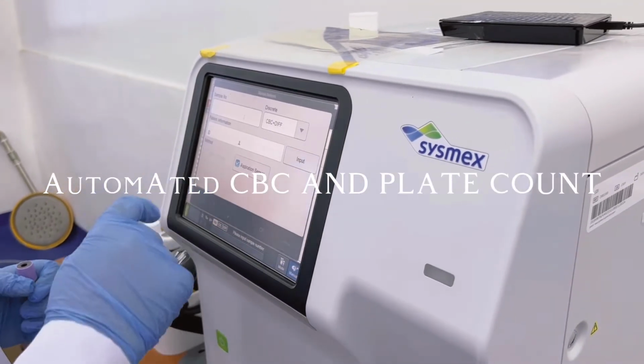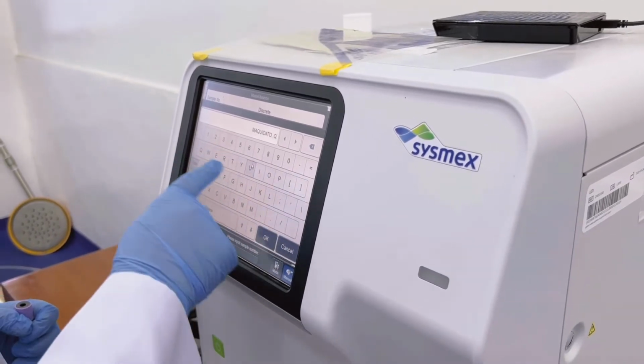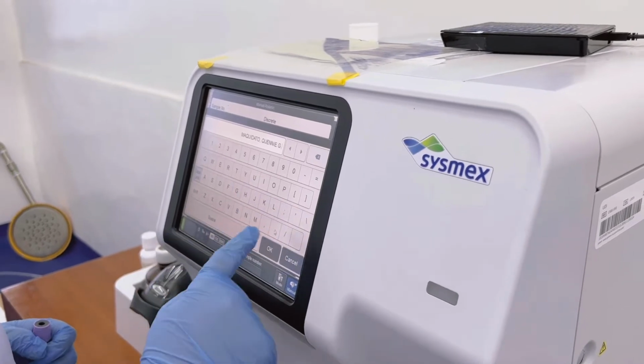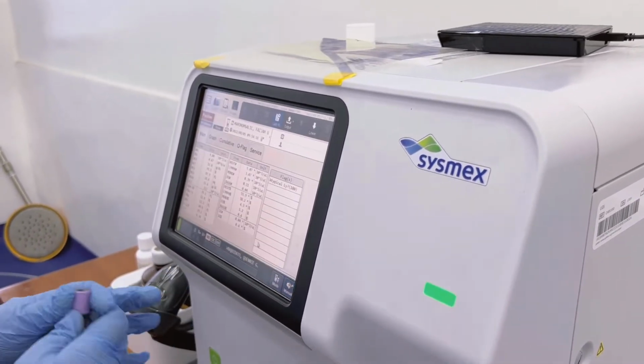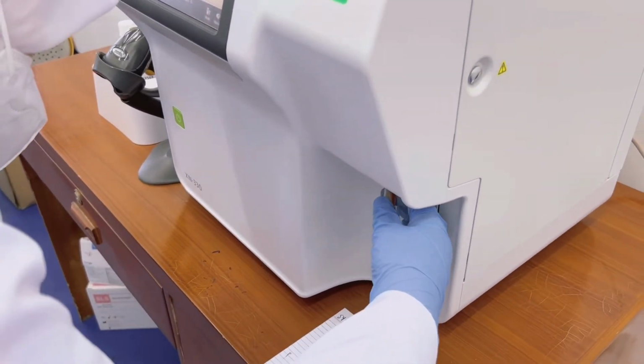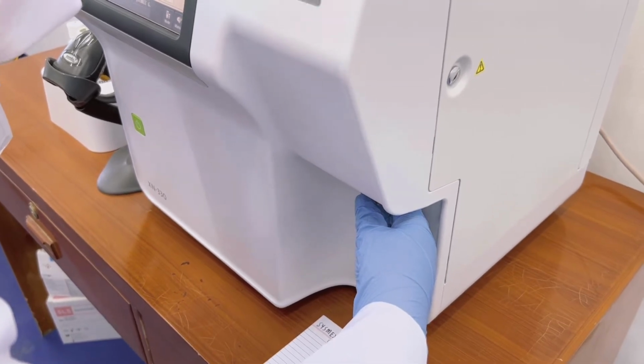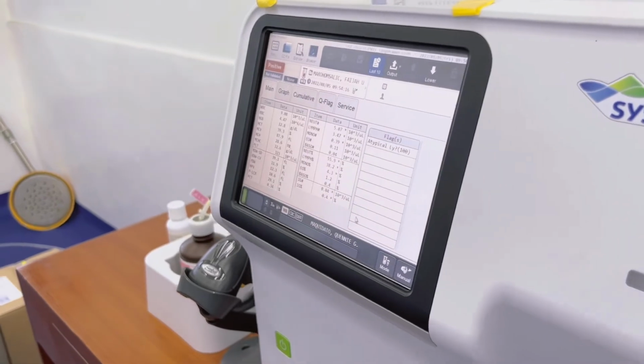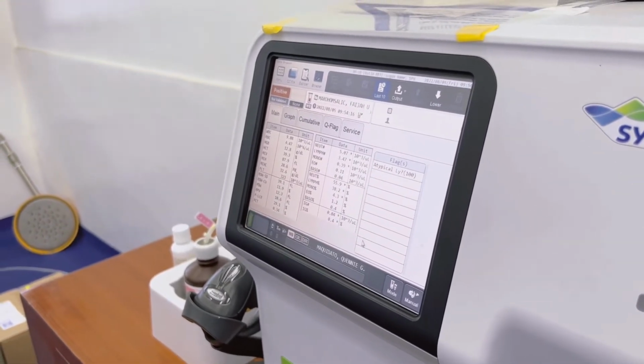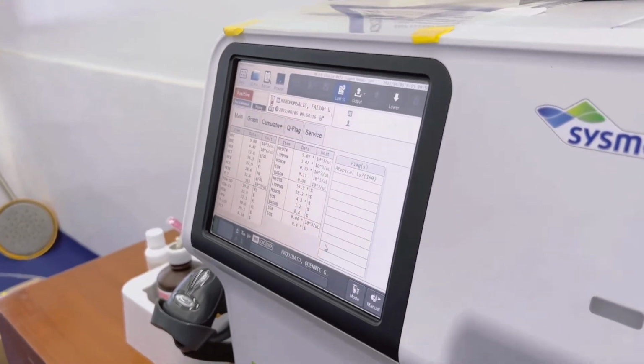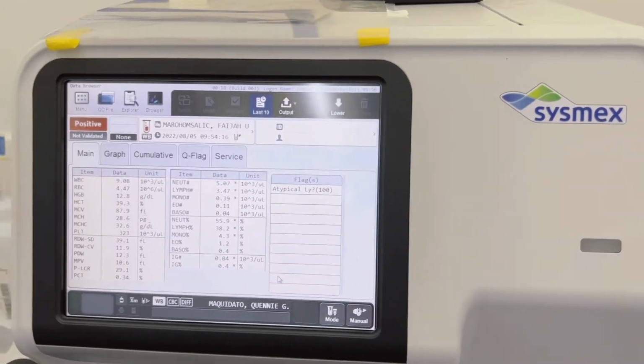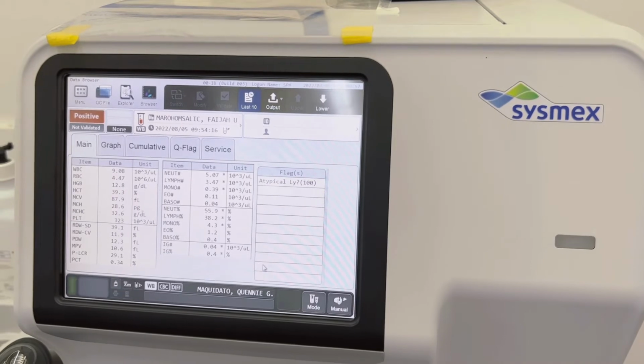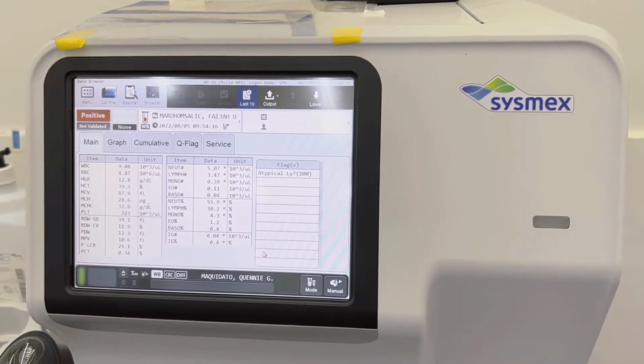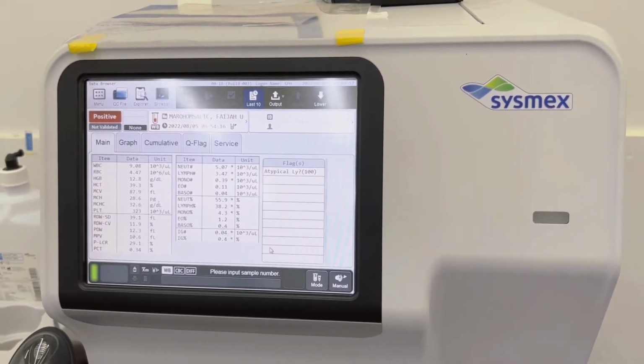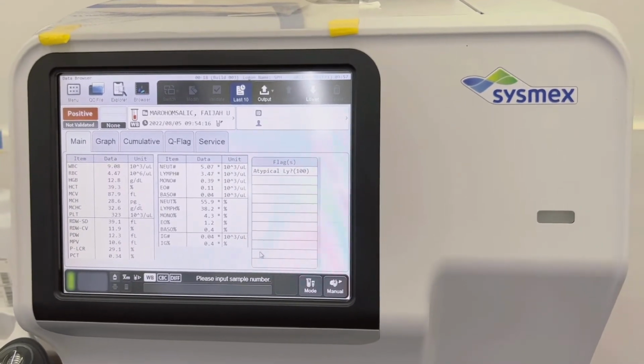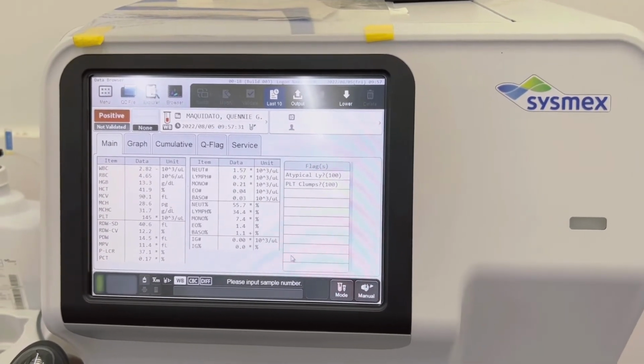Automated CBC and platelet count using Sysmex. First step is to input the patient's information into the machine. Next, you would see a green light which indicates that the machine can aspirate the sample now. Just click the button. After, you would hear a sound which indicates that aspiration is done. After a few seconds or a minute, the results will be flashed on the screen. Now the result is out, record the result into the form.